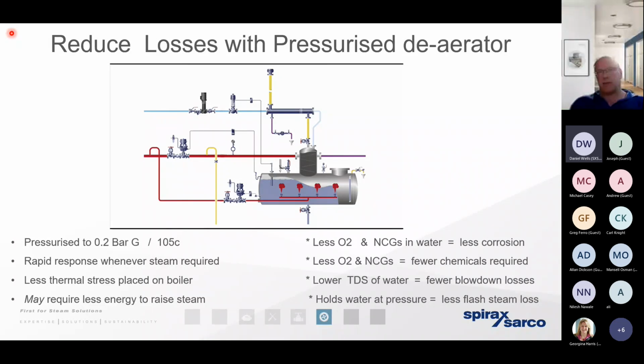Now, many steam using sites are familiar with holding the water atmospherically in a hot well or a feed tank, but by elevating the pressure to somewhere around 0.2 bar gauge, it means we can elevate the temperature of the water to 105 degrees. So we've got even hotter water going into the boiler. Therefore, we need to consume even less fuel to raise steam again. Other benefits include an improvement in water chemistry, which means we don't have to blow down as much hot water from the boiler. So we've reduced the thermal losses there.